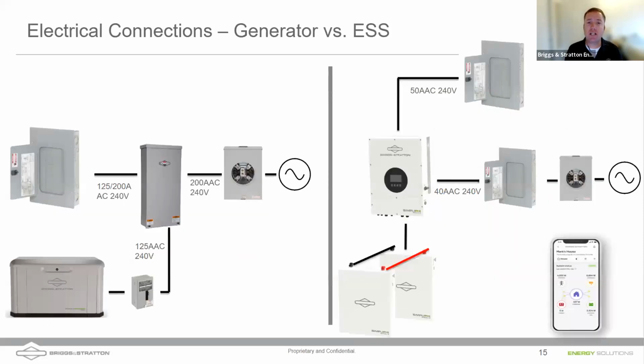One thing, as we're talking about how this works, is this is usually what it looks like when we do generators on the left-hand side. Usually we have grid going through a meter can that's passing through our transfer switch directly into our whole home backed up loads. If the grid fails, the generator is going to start, that transfer switch is going to switch, and now we're going to use a generator to start powering the backed up loads in the home. On energy storage, it's a little different. What we usually do, and it's not always the case, we can definitely do whole home backup with the energy storage, and we're going to look at that here in a minute.